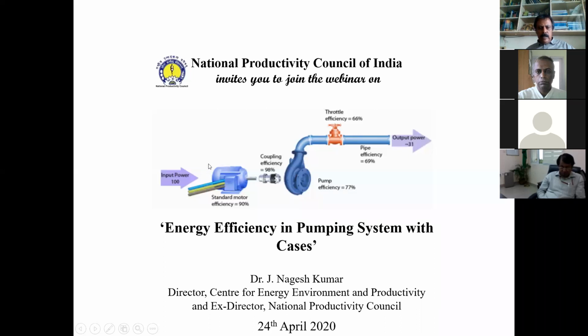So as we know, here is an electric motor which is driving a pump, and the pump is discharging some water at a particular pressure which is required for some process purpose. Now, what determines the power drawn by the motor? As we have seen earlier, it is not the motor which determines the power. It is basically the amount of water that is required to be used and the pressure at which it is to be used. That determines the power of the pump. This is the output power of the pump, the power to be delivered by the pump. And the input power to the pump depends again on the efficiency of the pump. So there are some losses in the pump for which the input power needs to compensate. So the input power consists of some losses in the pump and the actual power, that is the hydraulic power that is delivered to the process.